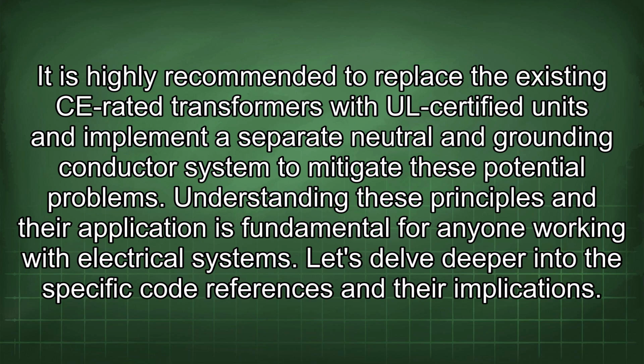It is highly recommended to replace the existing CE-rated transformers with UL-certified units and implement a separate neutral and grounding conductor system to mitigate these potential problems. Understanding these principles and their application is fundamental for anyone working with electrical systems. Let's delve deeper into the specific code references and their implications.